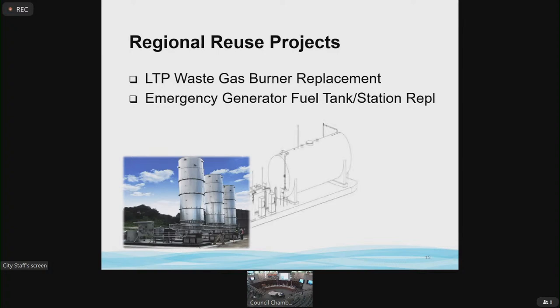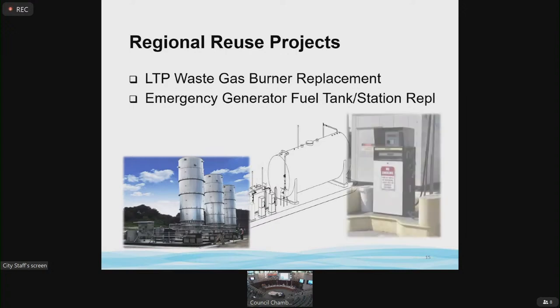This is in pursuant to PG&E's unpredictable frequency in implementing its public safety power shutoff, aka PSPS. So the plant identified the need to replace its aged diesel fuel emergency generator fuel storage with new above ground storage tanks, a new dual fuel diesel gasoline above storage tank, and a new fuel diesel gasoline dispensing station.